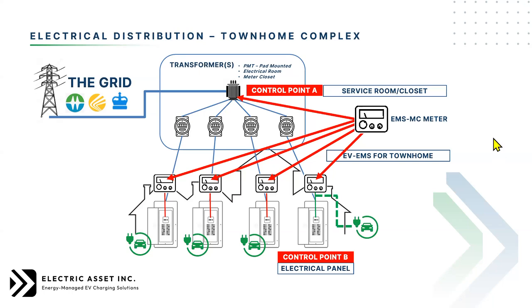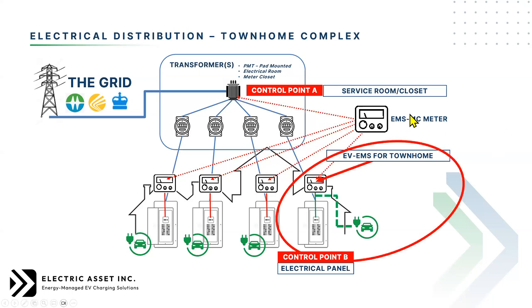And collectively what their impact is having on the centralized transformer. This allows the EMS to tell the EV EMSs installed in the townhome whether or not they have to turn down the chargers, not necessarily because the townhome panels are being overloaded, but because the main service might be overloaded. So through this device, you're considering all the safety features here.